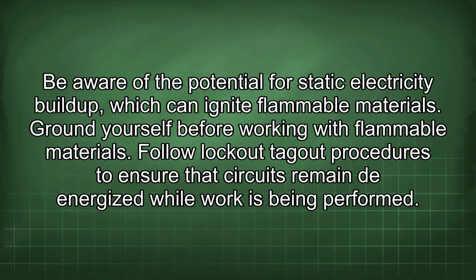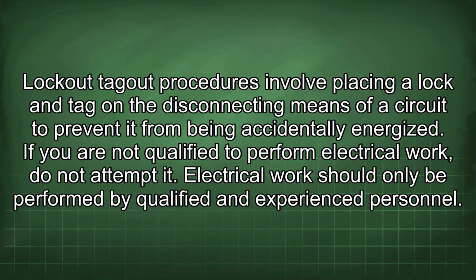Be aware of the potential for static electricity buildup, which can ignite flammable materials. Ground yourself before working with flammable materials. Follow lockout-tagout procedures to ensure that circuits remain de-energized while work is being performed.